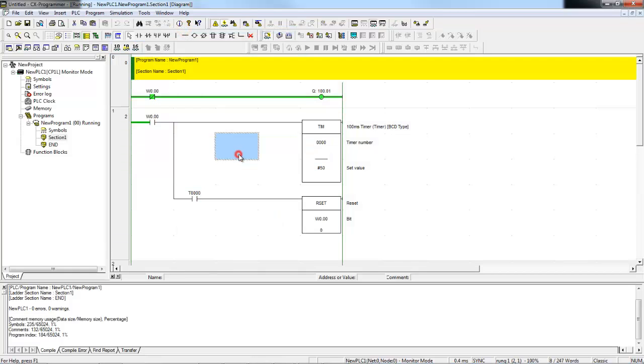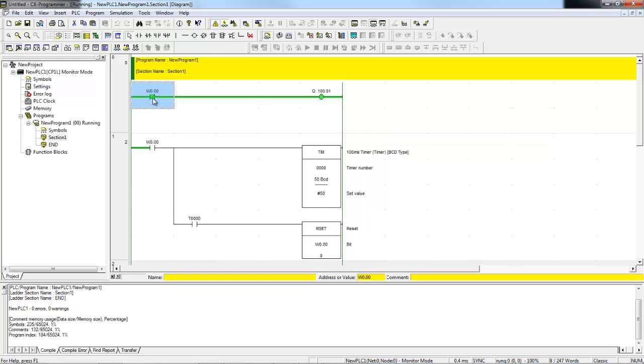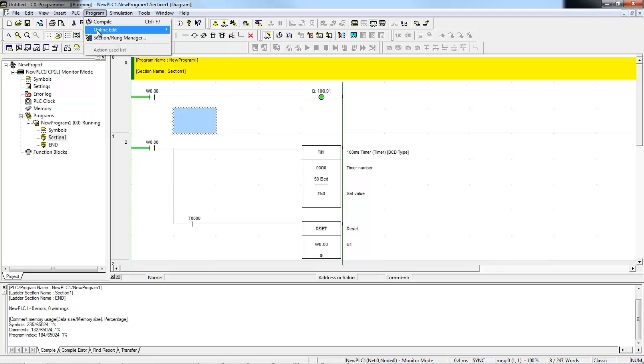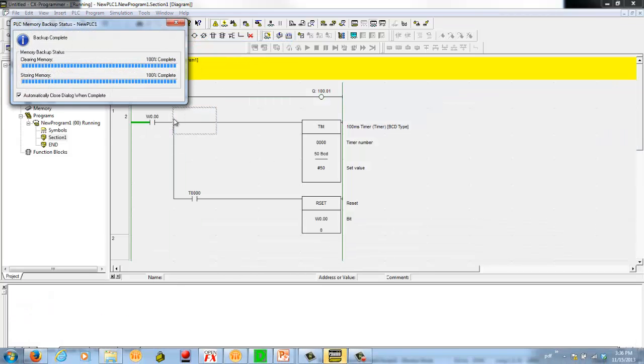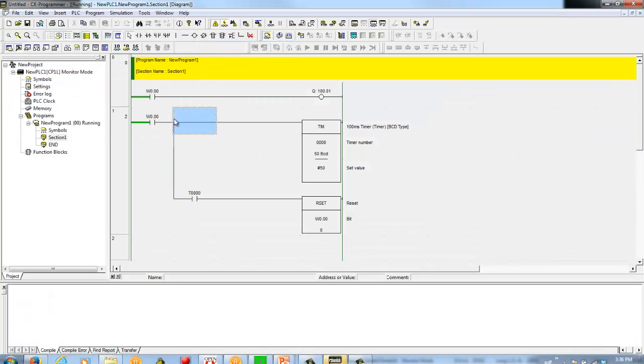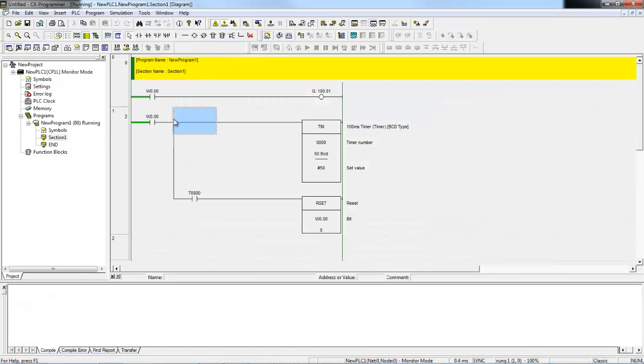And what happens is that section that I highlighted now turns white, and I could go and make an edit. I'm going to change this from Normally Close to a Normally Open contact. Once you've made your changes, back into the Program menu, I can do Send or Cancel. So I'm going to send these changes. So without actually having to stop the PLC, I was able to make an online edit and change the functionality of that contact.